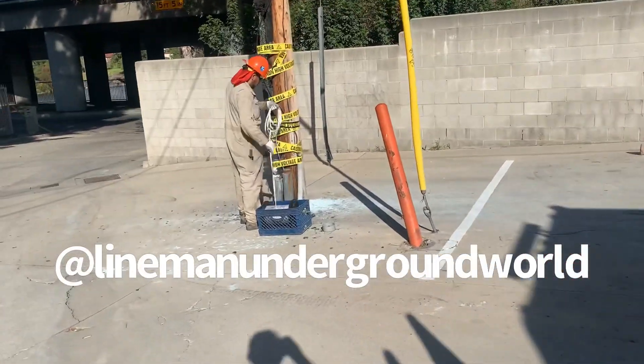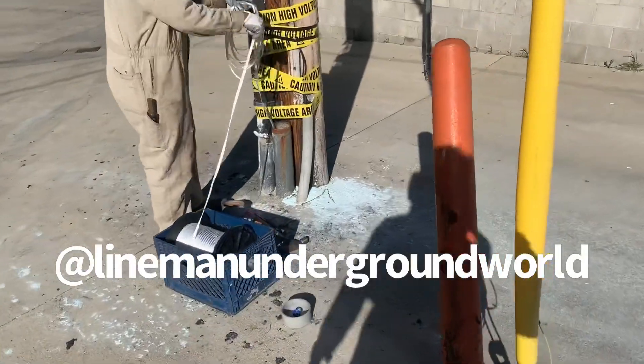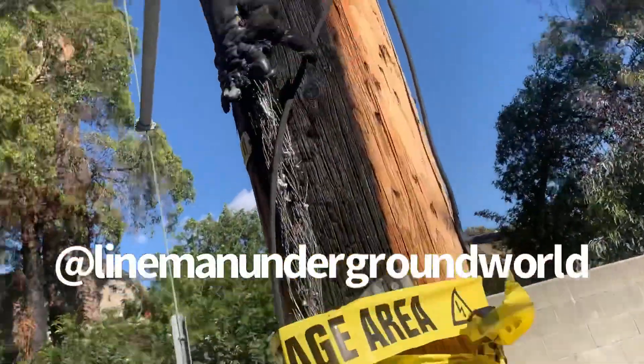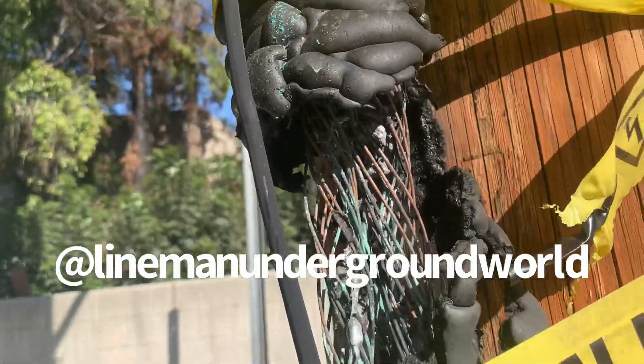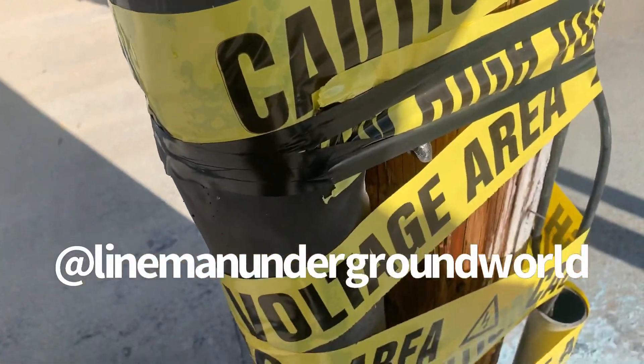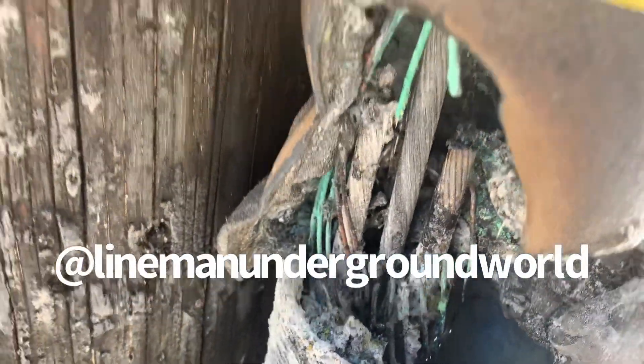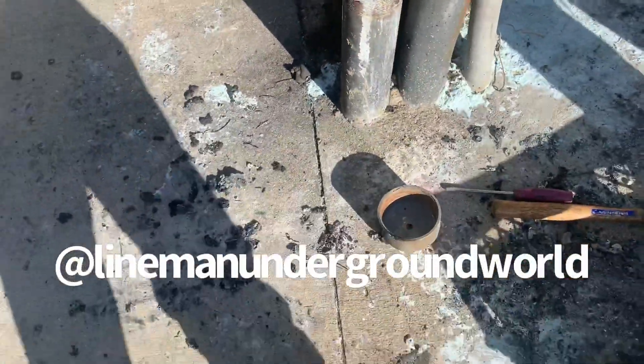Pulling on a flat line because all we had was that yellow pull line — we always try to use flat line for everything. And as you can see, once again we got a blown up riser — look at that thing. These guys are kind of cut into 4.8 kV thinking it's 120, and hopefully they survived or ran off.